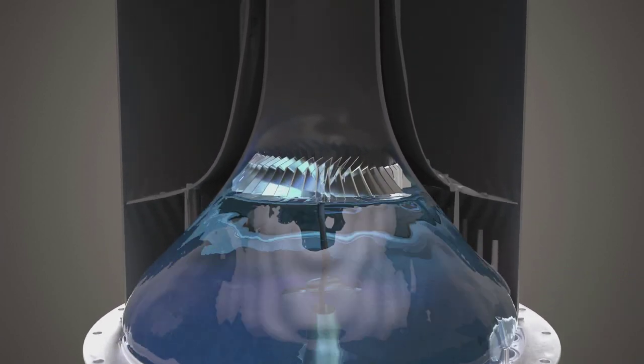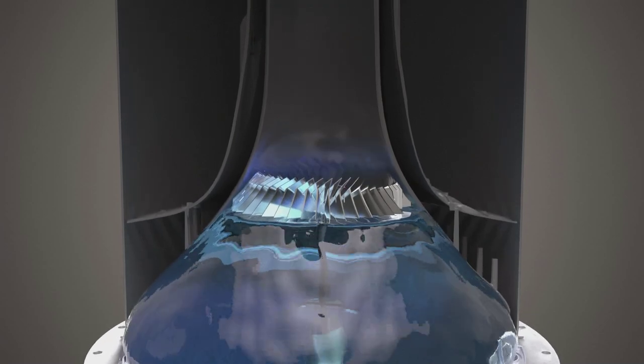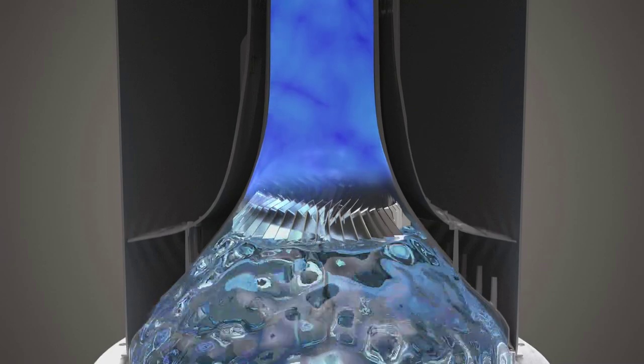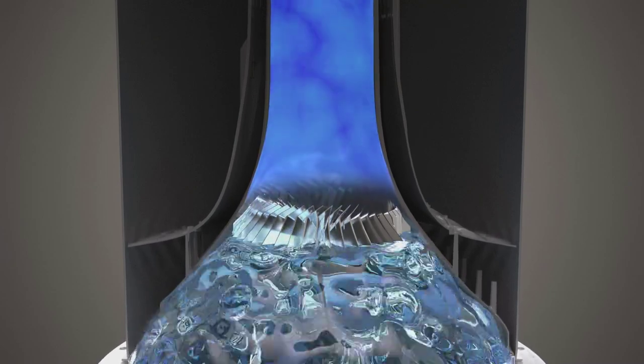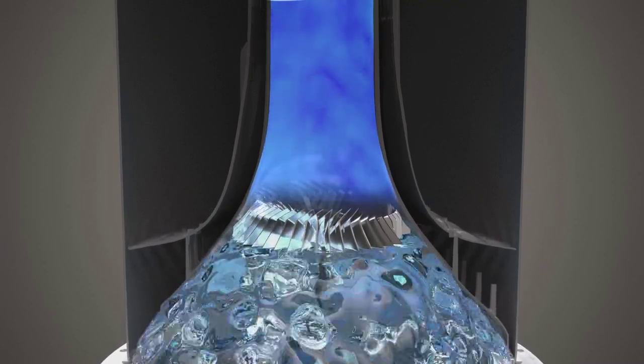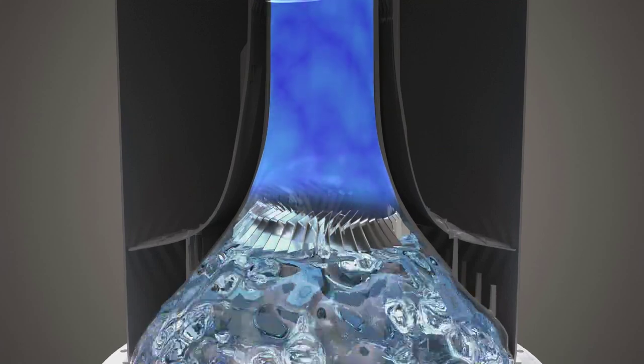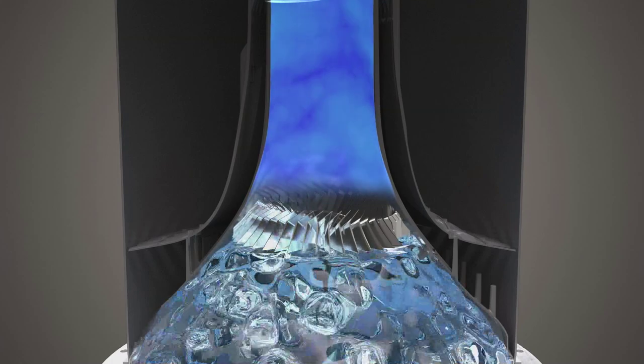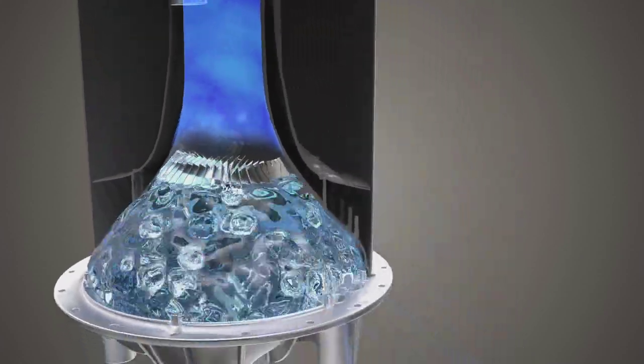Because the pressure is so low — just 60 millibars — the water immediately begins to boil and part of it passes into the gas phase. This removes heat from the still-fluid water, which, now cooled to 16 degrees Celsius, flows back towards the server to chill it.